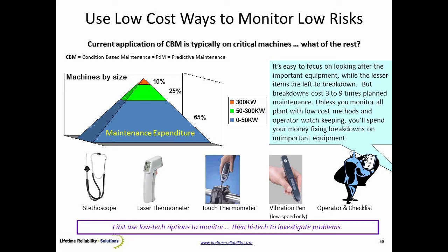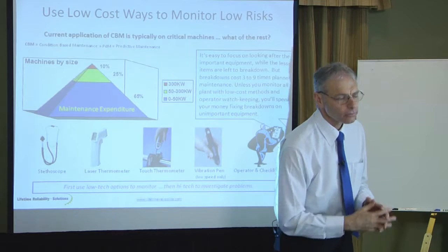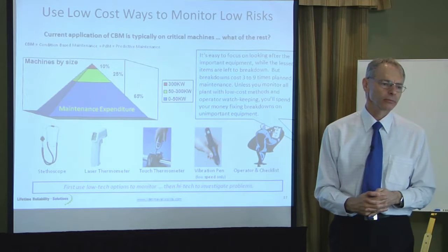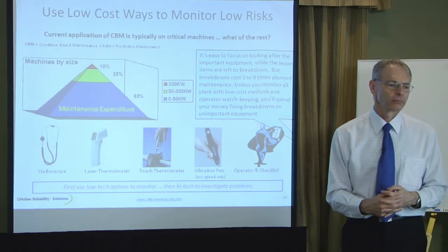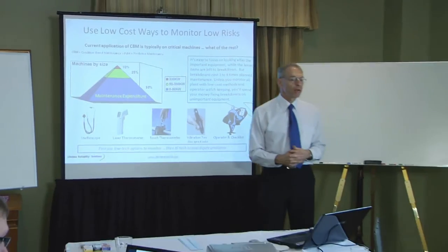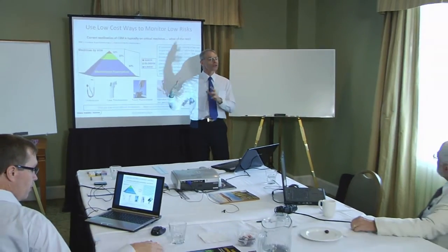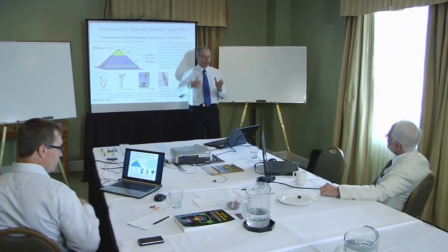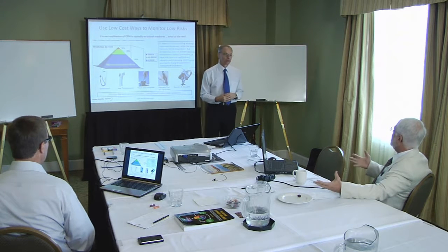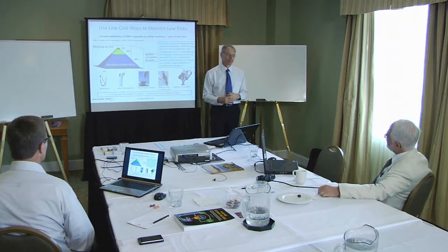So yeah, we're going to do smart things. Just got to know what those smart things are. On that pump issue, he needs to change alloys to get something that won't cavitate. That would be a fair question to ask as a long-term solution. Today, right now, with the cavitation he's got to fix his trouble today. But he's just putting the same pump back in, which will cavitate again.